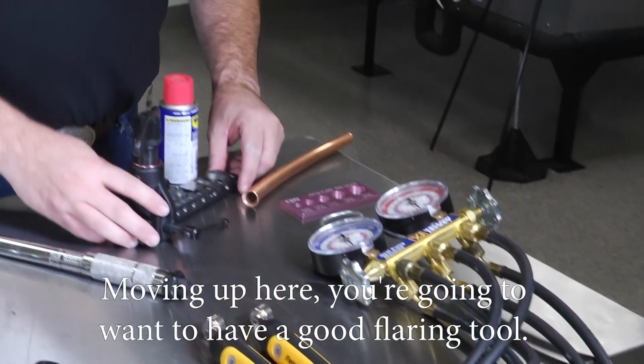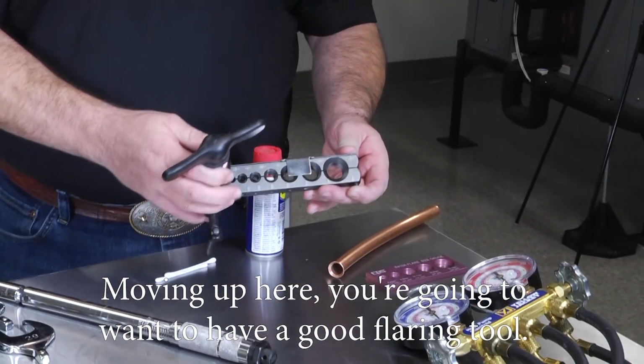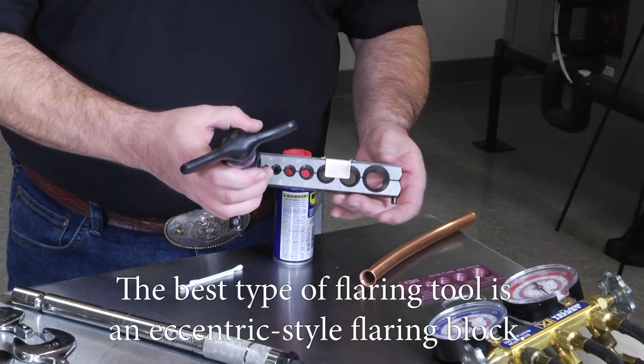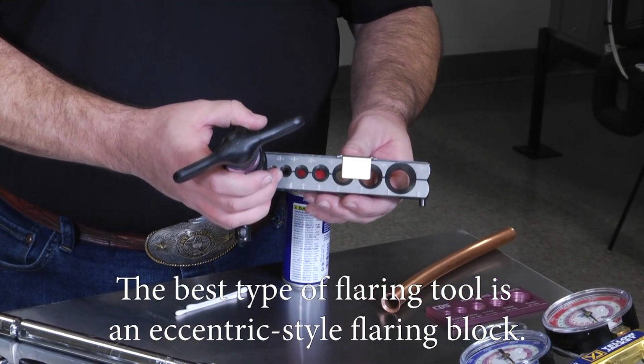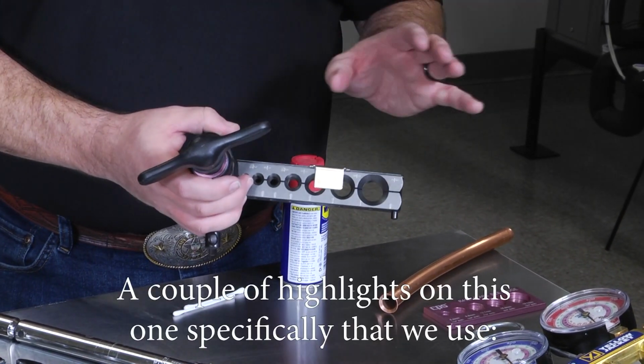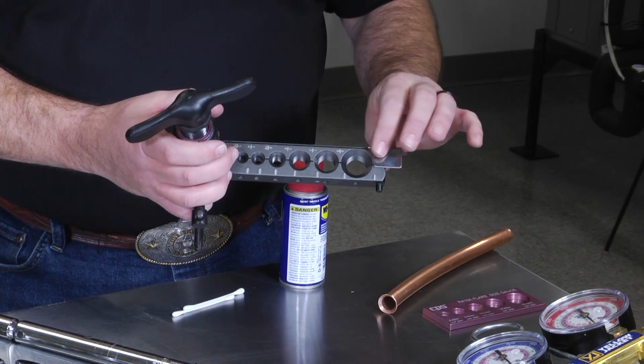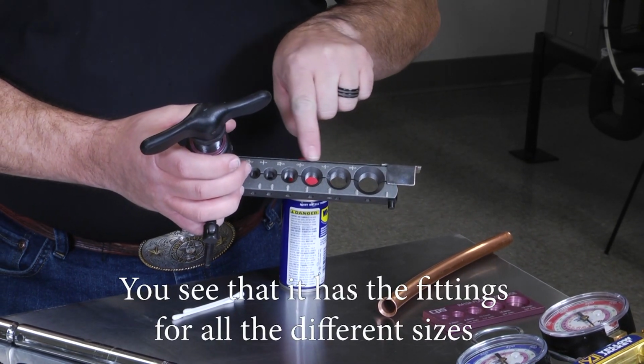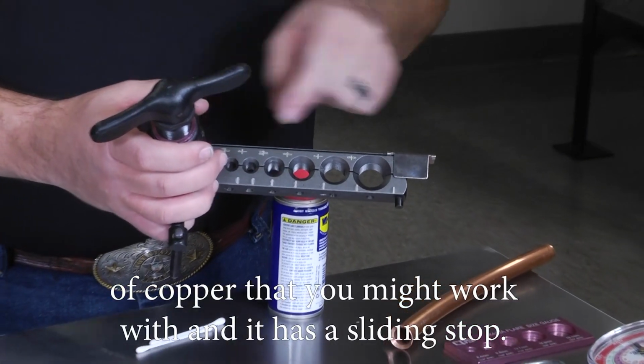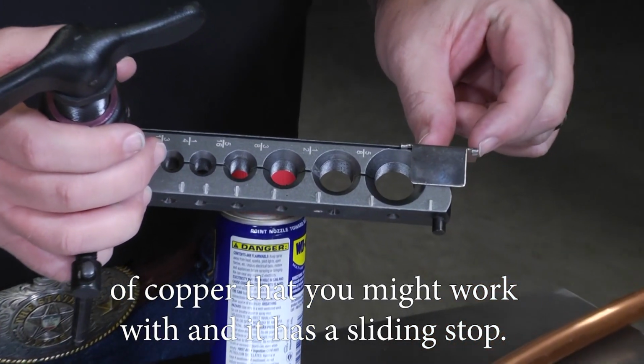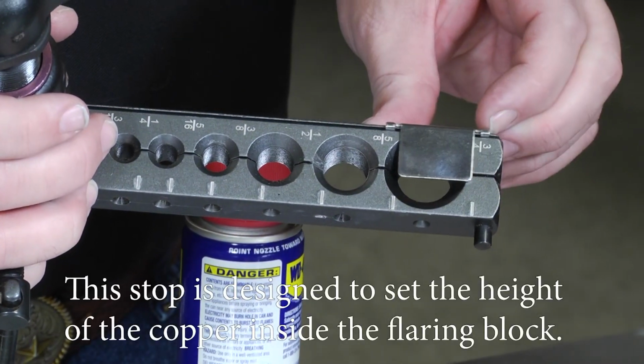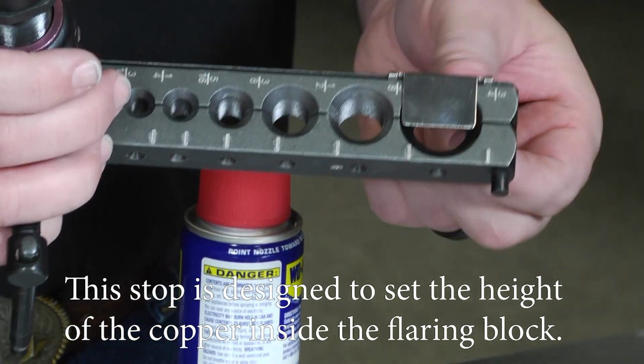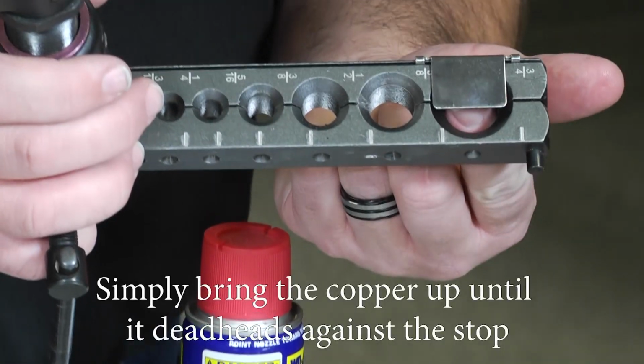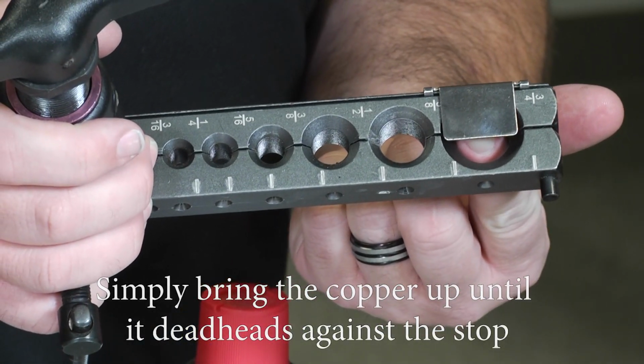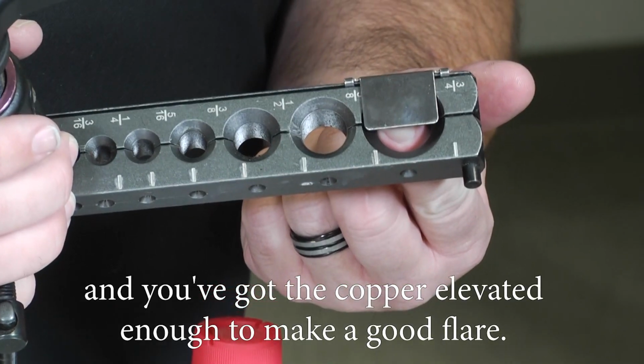Moving up here, you're going to want to have a good flaring tool. Now, the best type of flaring tool is an eccentric style flaring block. Couple of highlights on this one specifically that we use. You see that it has the fittings for all the different size copper that you might work with, and it has a sliding stop. This stop is designed to set the height of the copper inside the flaring block. Simply bring the copper up until it deadheads against this stop, and you've got the copper elevated enough to make a good flare.